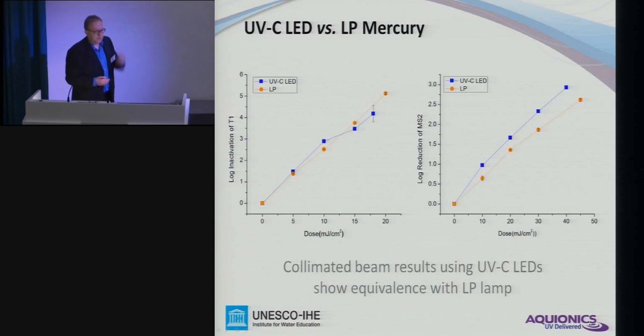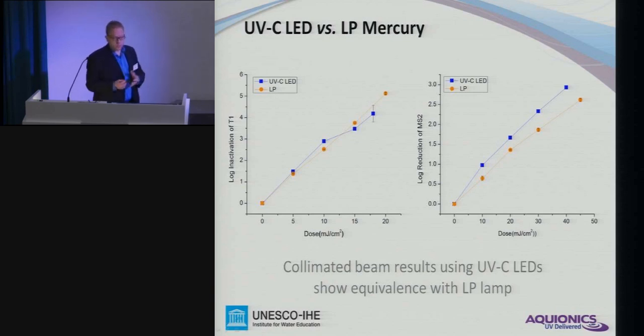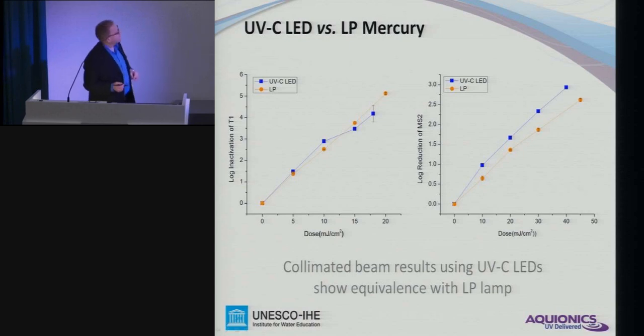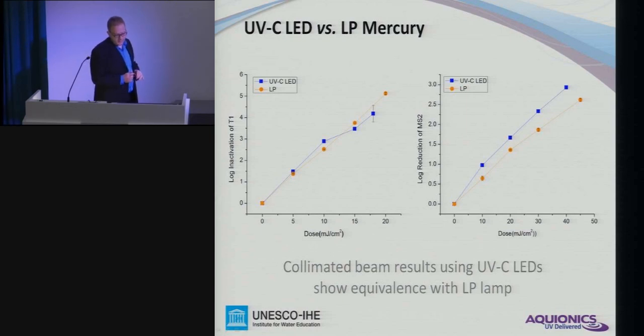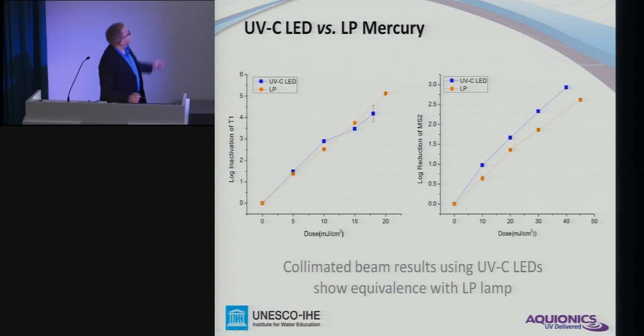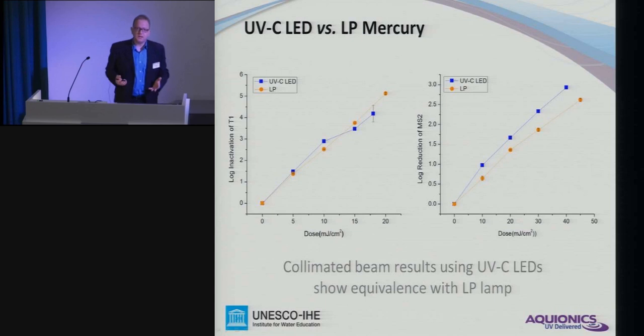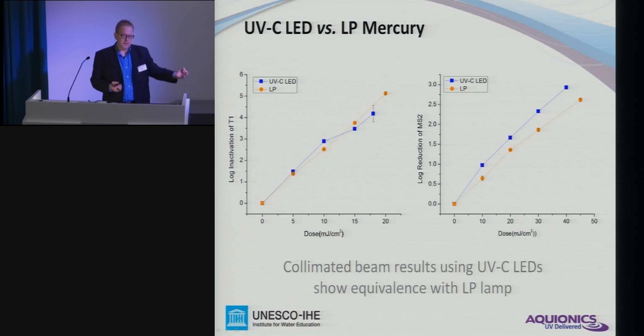Some work was done comparing the effectiveness of UV light emitted by LEDs versus low-pressure mercury-based lamps. The left graph shows inactivation of T1, the right one MS2 — surrogate organisms used in validation of UV disinfection systems. Based on a delivered dose on the horizontal axis, it results in a certain log inactivation, and the collimated beam results show that they are both equivalent. Technically, it doesn't matter to the bug if it's killed by photons emitted by an LED or by a mercury-based lamp.